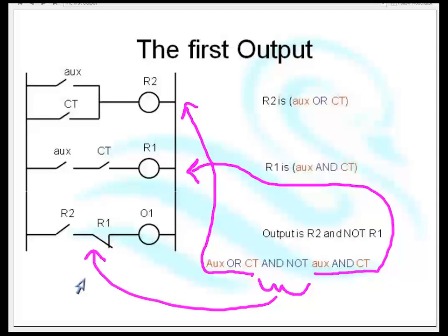So what we've just done is we've used the English language sentence to build a circuit. That's how we're going to do all of our programming, not just relay logic programming, but PLC programming. All programming is done using the same method. You look at the output, you write down an English sentence which explains when you want that output to come on, and you look for the special words: and, or, not. Whenever you see and, that means two switches in series. Whenever you see or, that means switches in parallel. Whenever you see not, that means grab the normally closed contact.